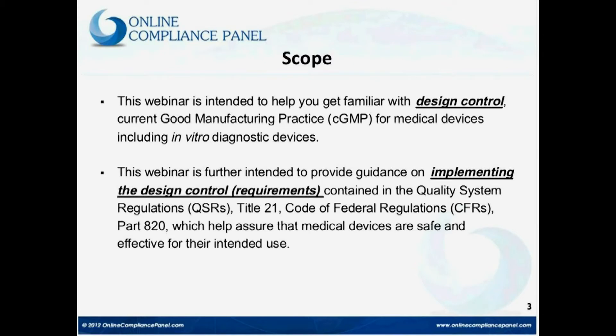CGMP is the Title 21 Code of Federal Regulations, CFR Part 820. This webinar is further intended to provide guidance on implementing the design control requirements under 21 CFR Part 820, that is the quality system regulations, which is equivalent to CGMP for medical devices as well as IVD.